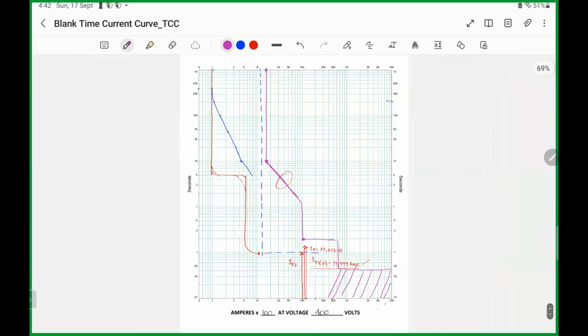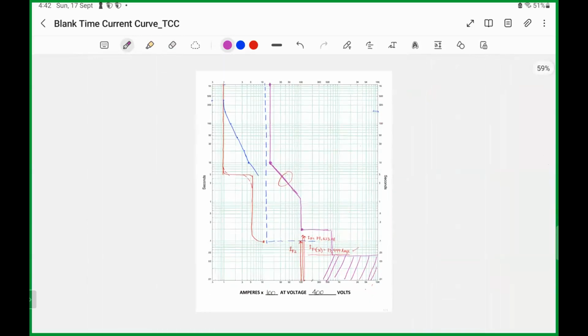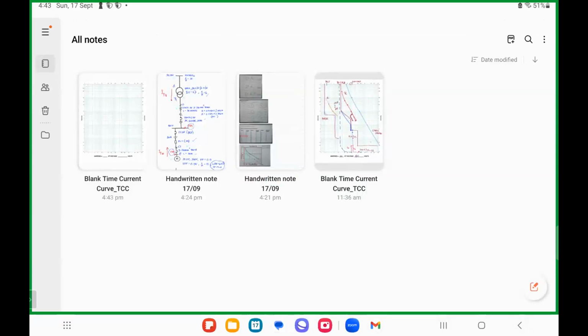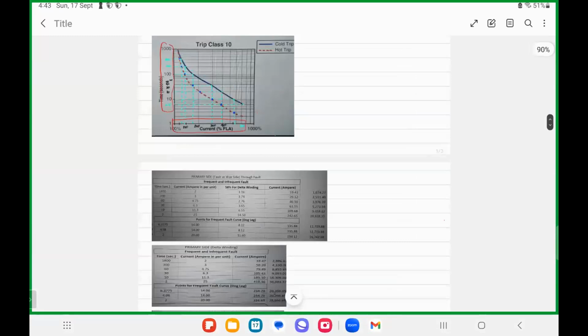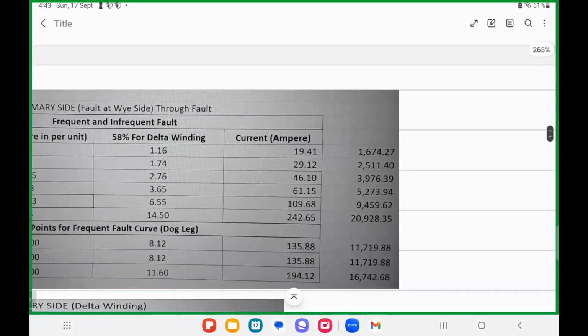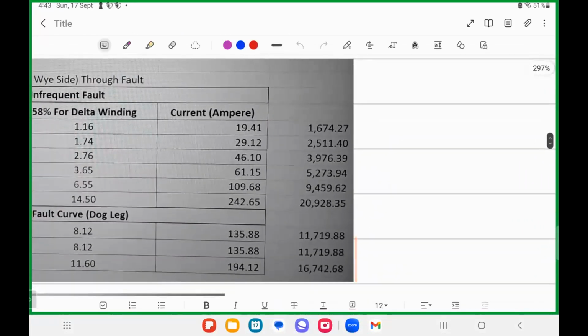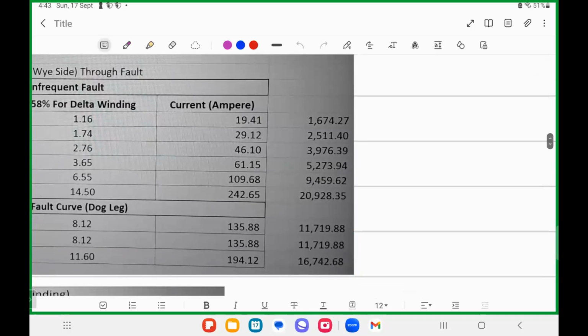Okay? So next, if we have the transformer, based on what we did earlier in the presentation, where we have a table that we use with direct substitution, you just multiply the per unit values of the transformer category by your full load current. You can plot the transformer curve, the damage curve. But let's look first at the damage curve. Let me find the transformer that we used. This one. So this is the per unit, 1.0 per unit of the fault current at the downstream or the main bus. I calculated it based on the per unit given in the table by category. Our 1 MVA transformer will fall under category 2.